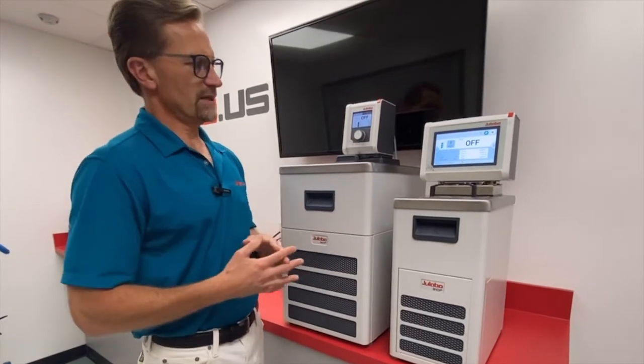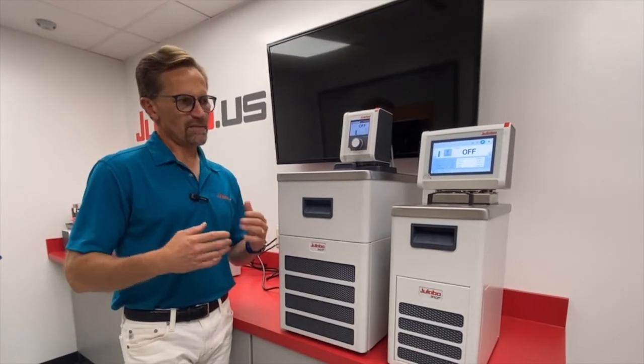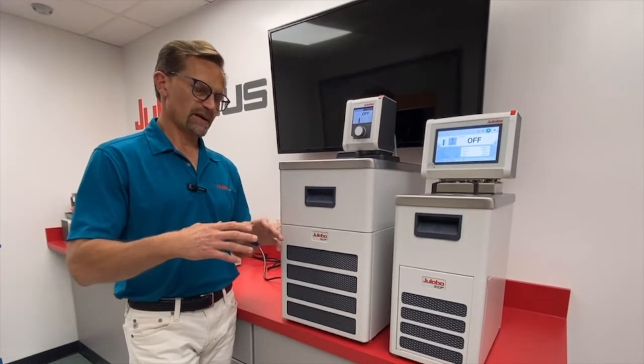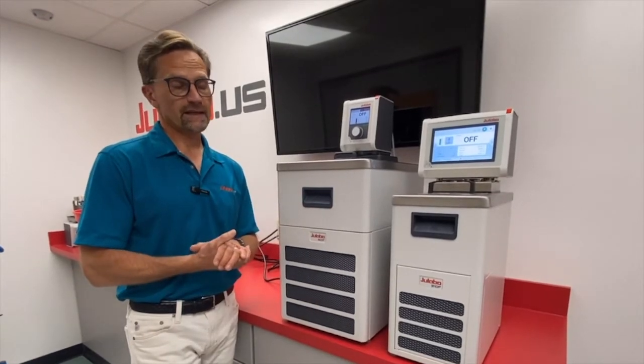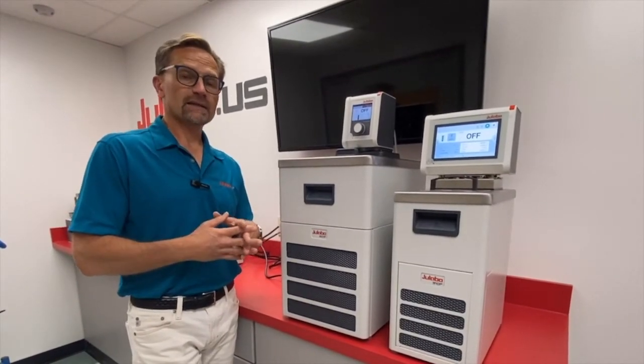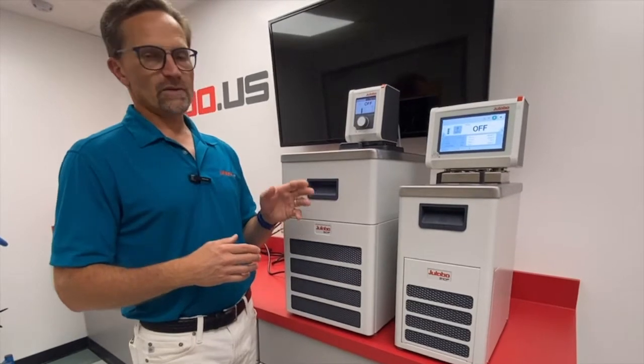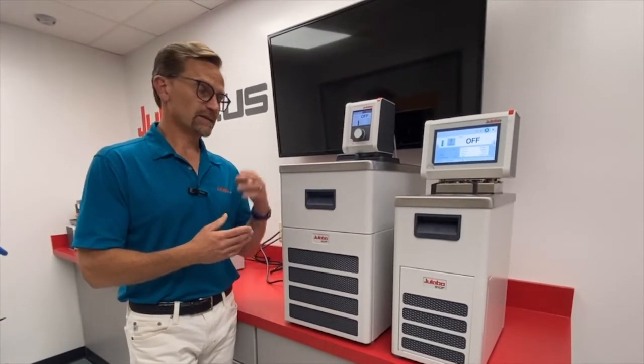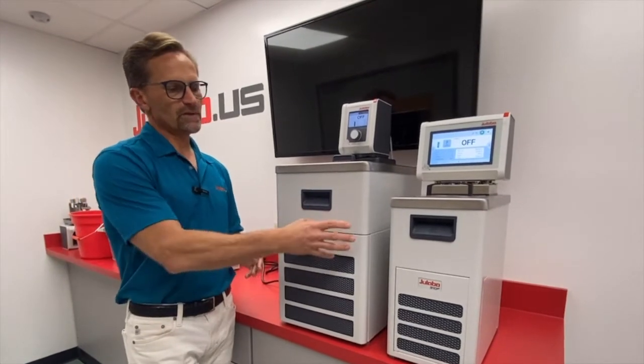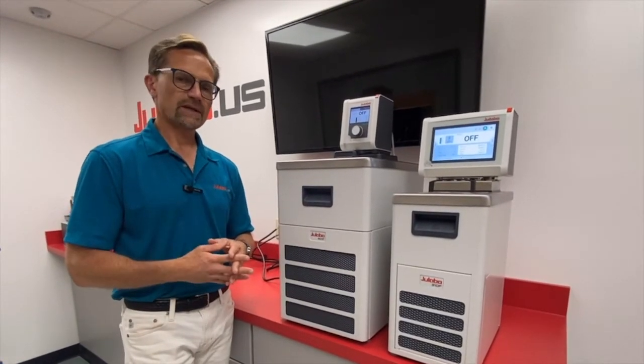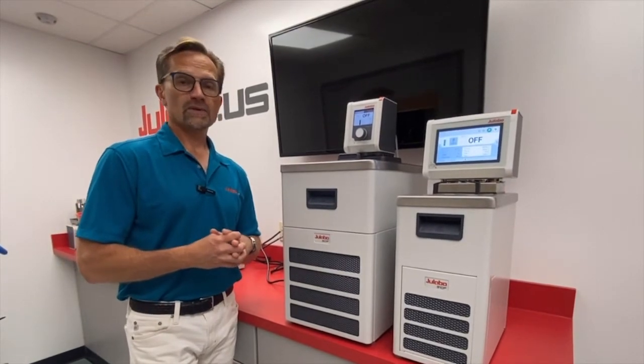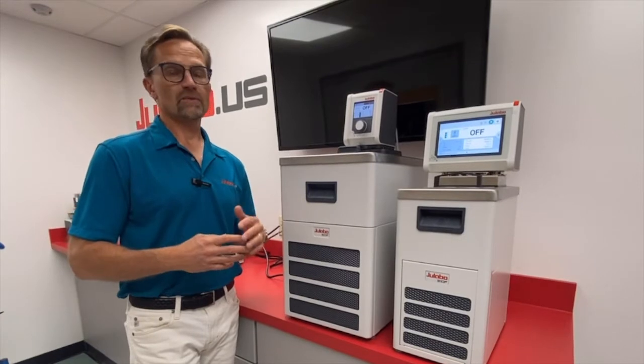So the MAGIO, in comparison, has 2 models where the MAGIO MS can come as an immersion circulator on an adjustable bridge or 4-liter heating tank, and the MAGIO MX comes with 6, 12, or 26-liter tanks. Both of the MAGIOs have a temperature limit up to 300 degrees C for heating circulators. And they have either 1 or 2 kilowatt heating power for the MAGIO MS, similar to the DYNEO units, but the MAGIO MX has a 3 kilowatt heater. It can also be paired with refrigeration units. We have 5 models available, ranging in temperature from minus 30 to 200 degrees C down to minus 50 to 200 degrees C, with cooling capacities starting at 220 watts up to 1 kilowatt.